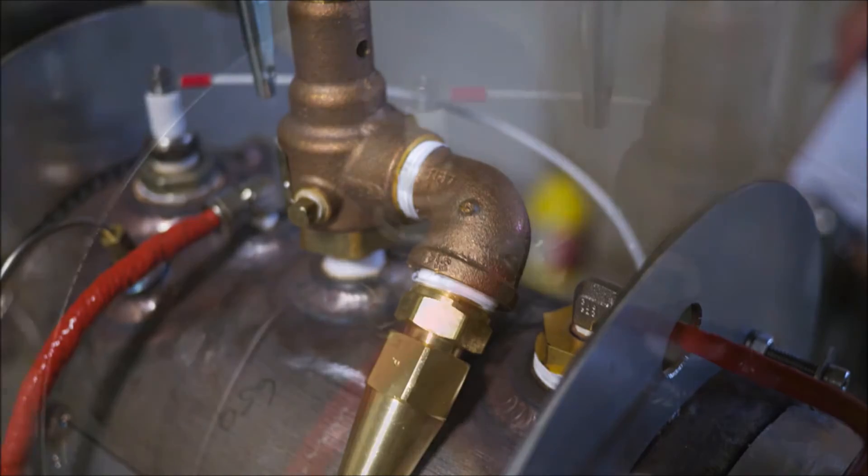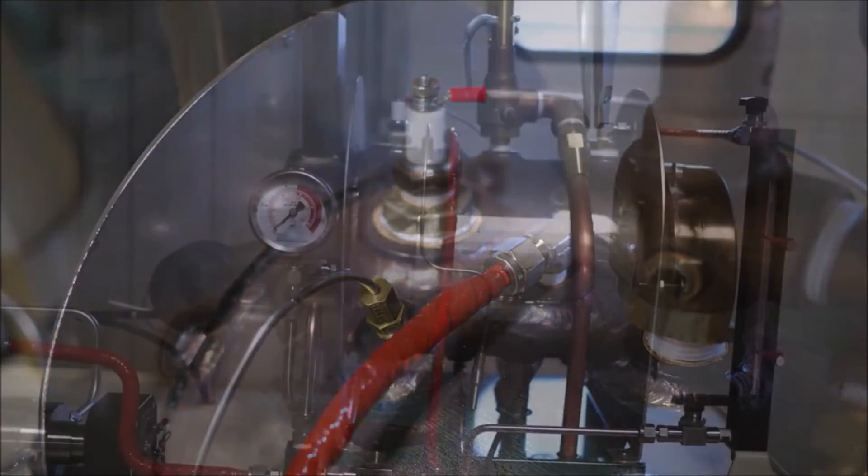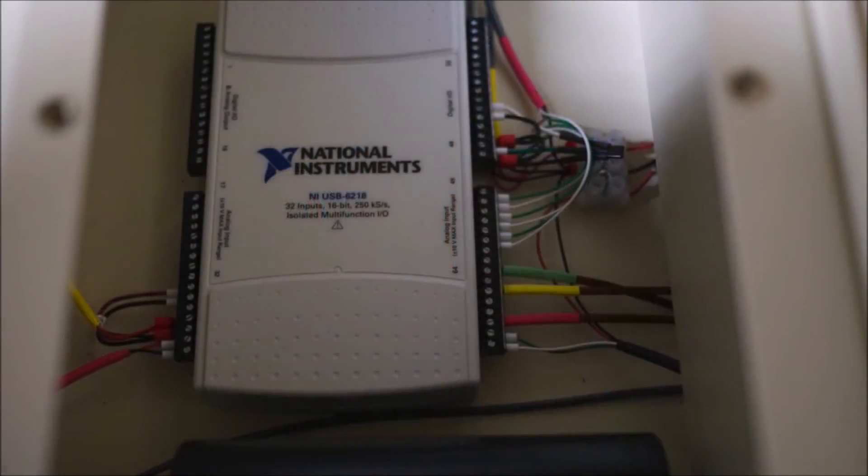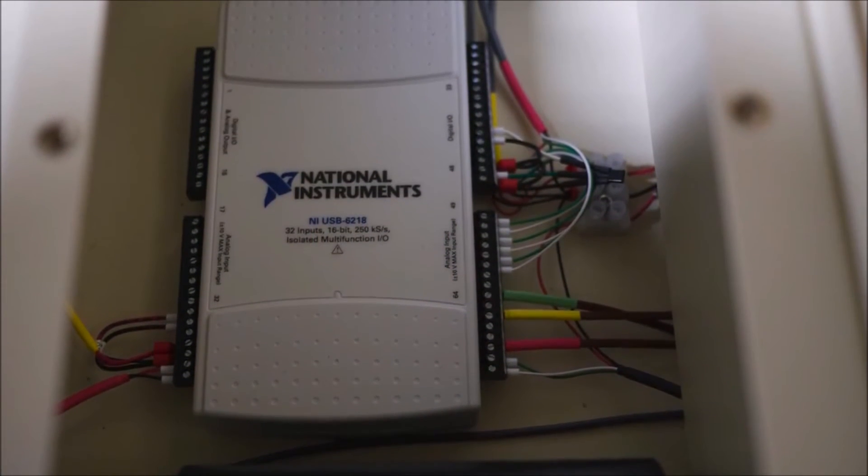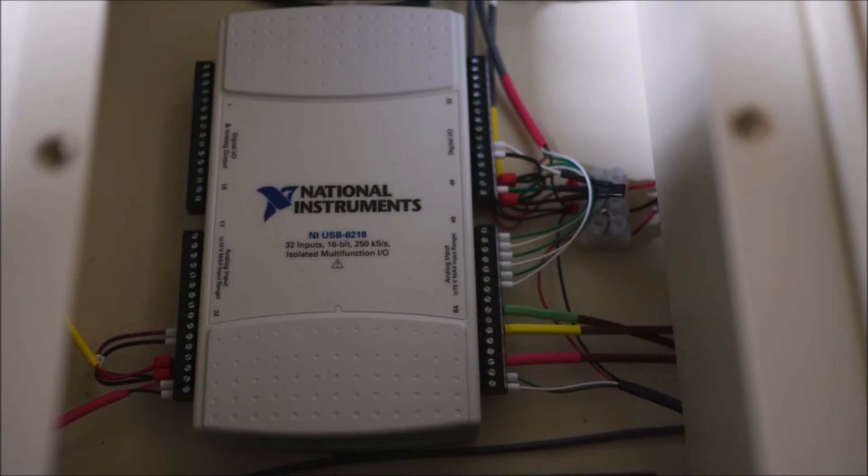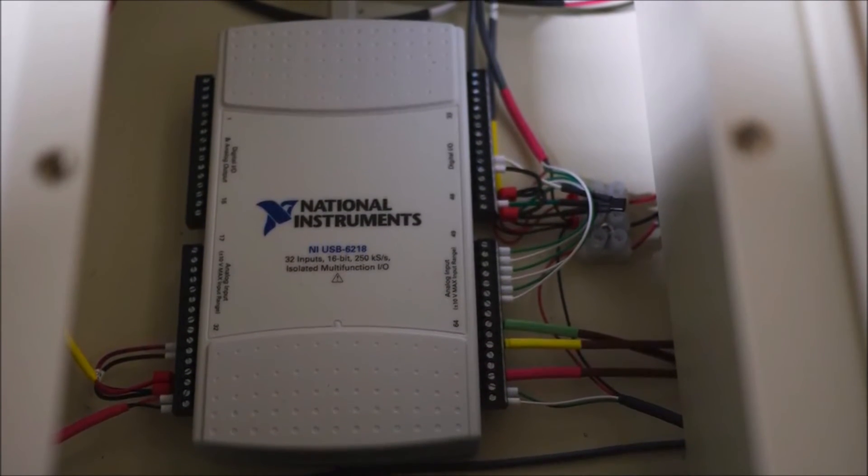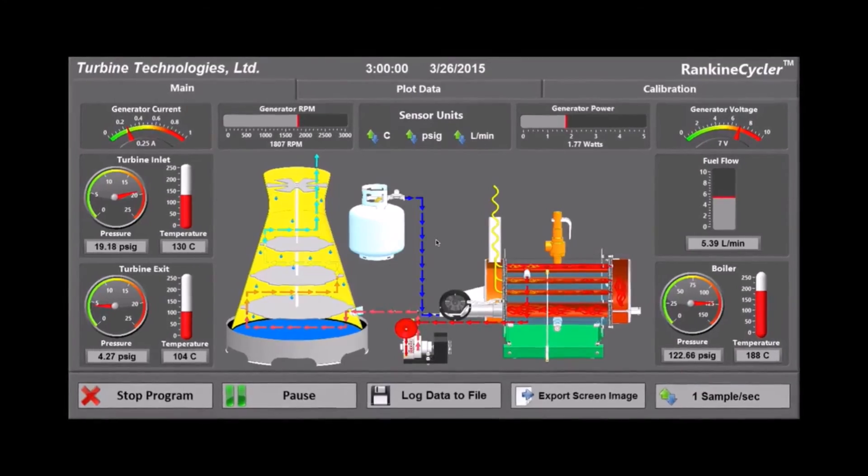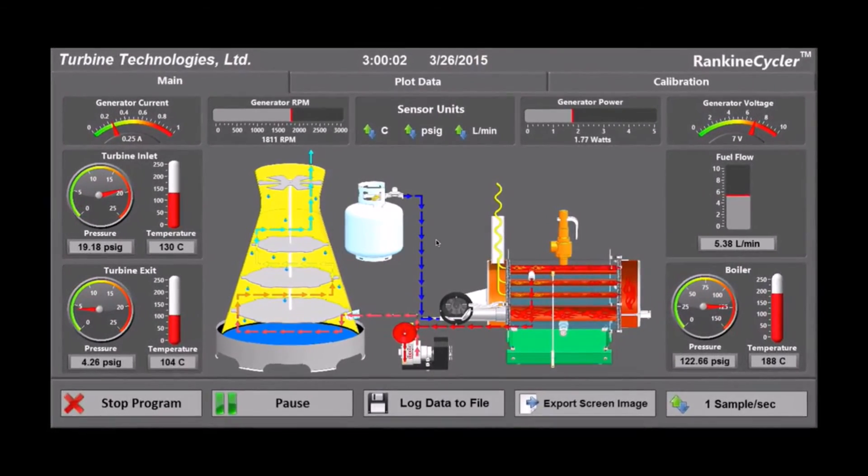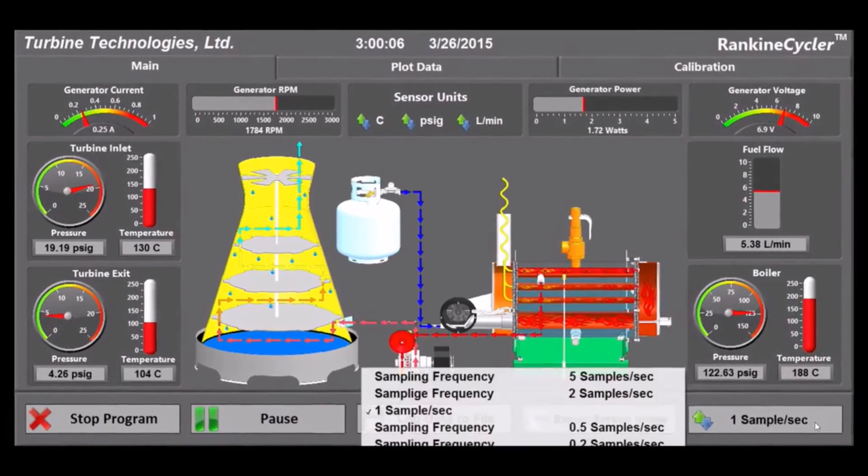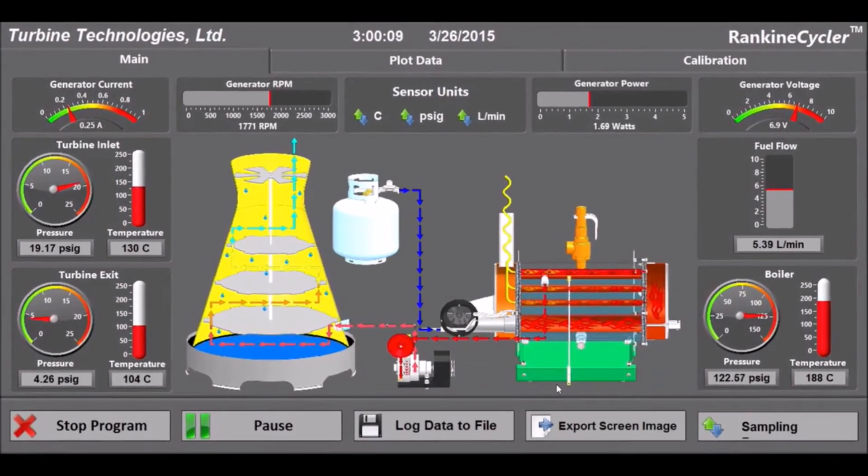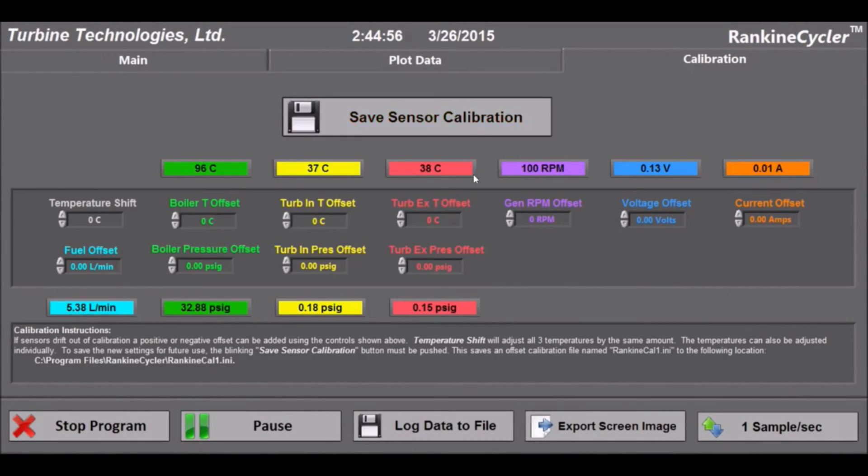Strategically integrated sensors measure system operating parameters and send that information to a USB-connected National Instruments Data Acquisition System. This pre-calibrated DAQ system records sensor data for later manipulation and sends the data signals to a LabVIEW-generated virtual instrument panel for real-time sensor display on the provided laptop computer. All data acquisition and display software is user-configurable and all source code is open.